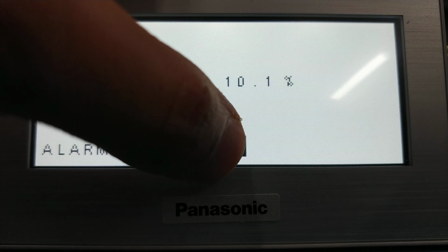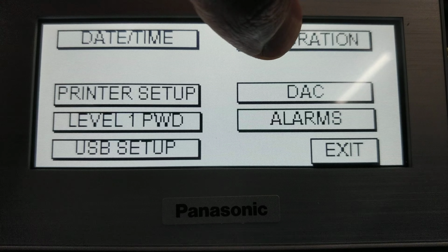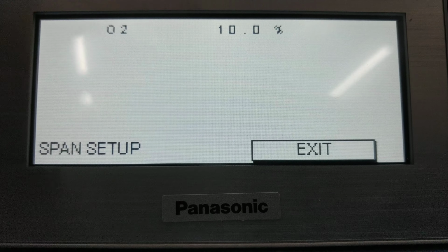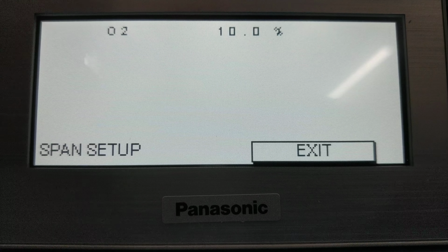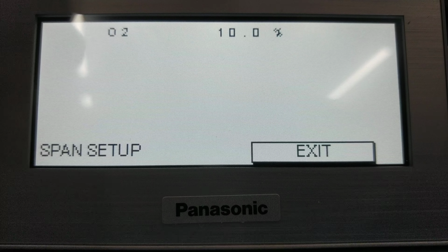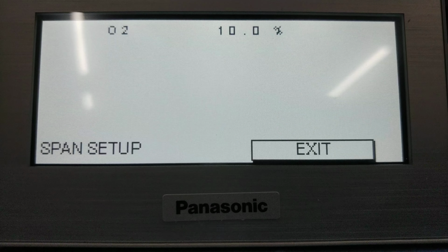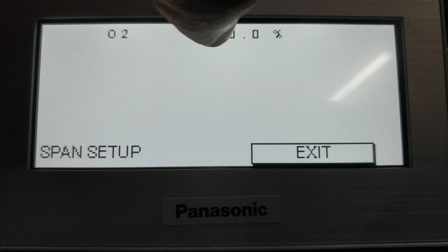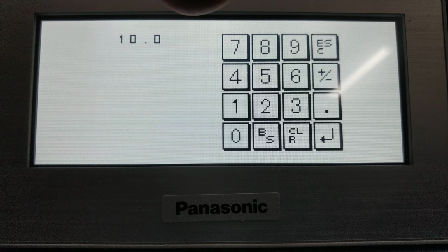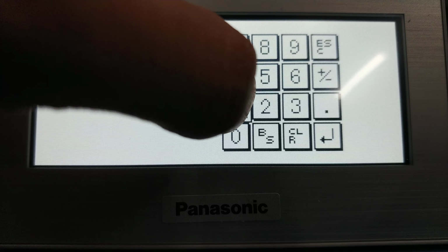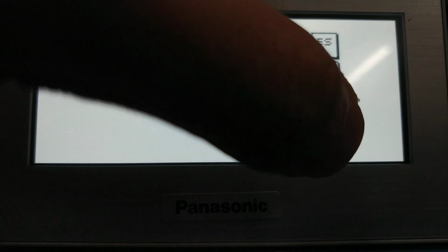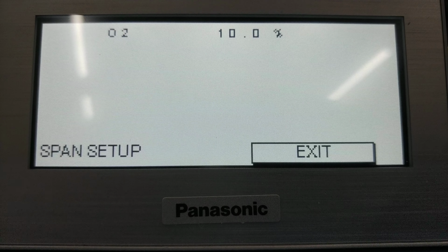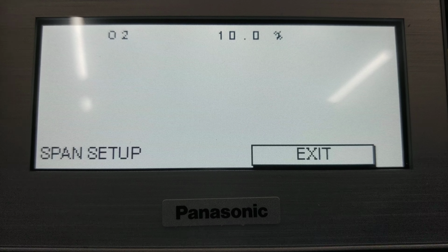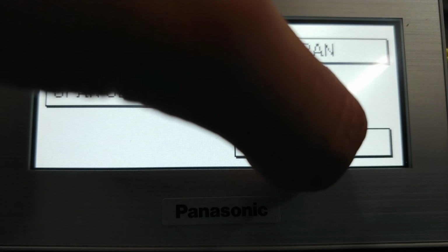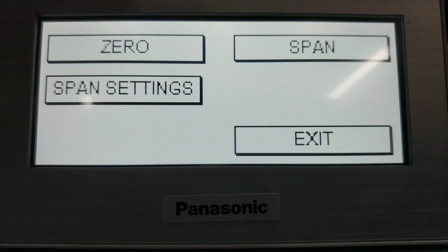So the first thing you want to do is make sure your span settings are correct. So you go to setup, calibration, span settings. You put here what the value of your O2 content is in your span calibration cylinder. In our case, I've put 10% because that's what we're using to simulate. So if you want to change it, you would just press this number and put in whatever value you want. So just to demonstrate, I'm just going to put in 10 again. So 10, 0, and I'm going to press enter. That's it. So now I'm good to go. This is what I'm going to use to do a span calibration. I'm going to exit.